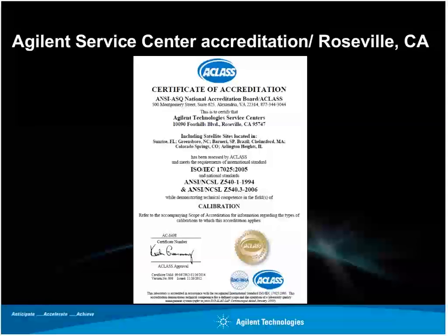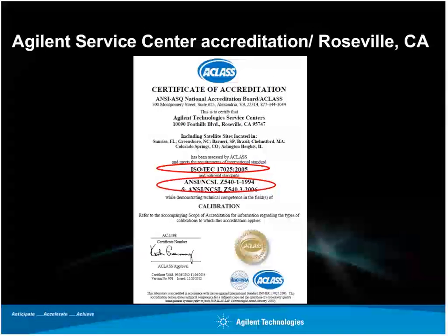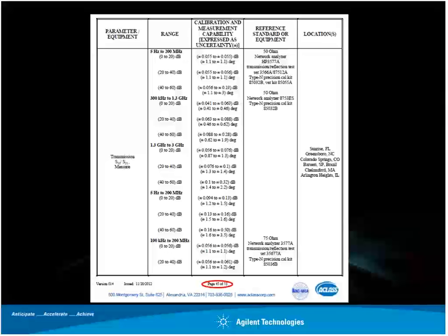The certificate of accreditation shows the standard to which people have been accredited. In Europe, it's almost invariably 17025, although there are some medical laboratories for 15189. In the US, you will also get the Z540 series accreditations. But as I mentioned earlier, that certificate's fine, but you need the scope as well.